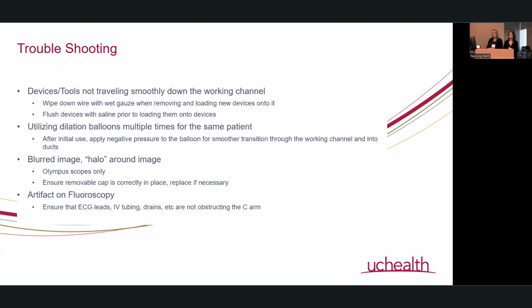Blurred image or a halo around the image when you're using this scope, it's usually, I mean, we stated here it's Olympus scopes only. I'm not for sure 100% about that, but we did state that. And then ensure that the removable cap, which was in the previous picture, is correctly placed. And if that isn't, and you still have that halo, we'll actually remove the scope, replace that cap, and then start again.